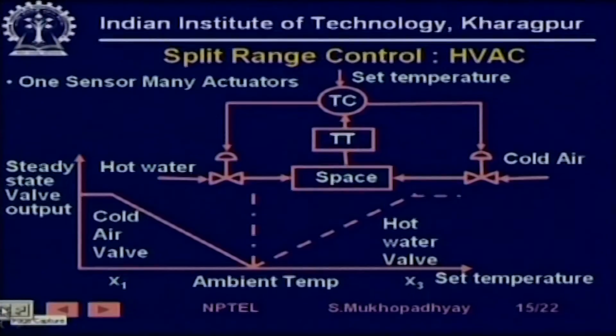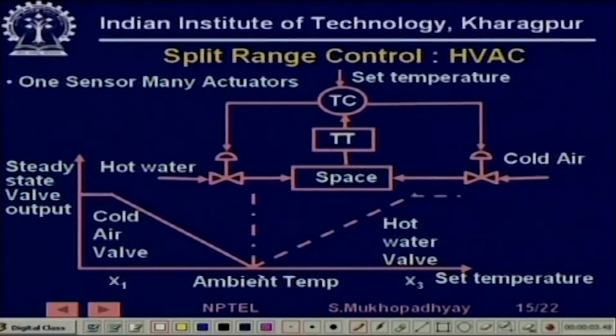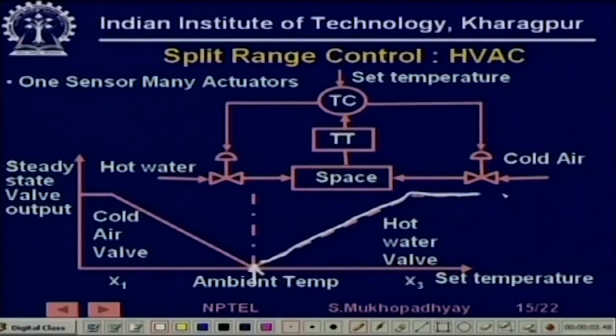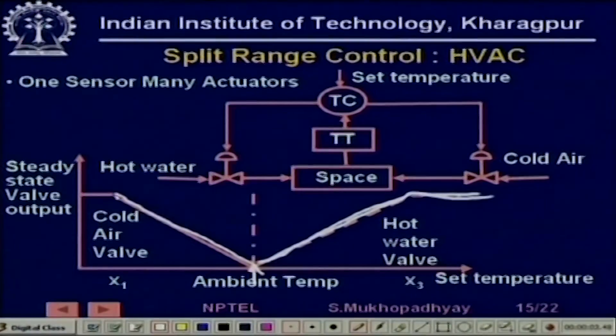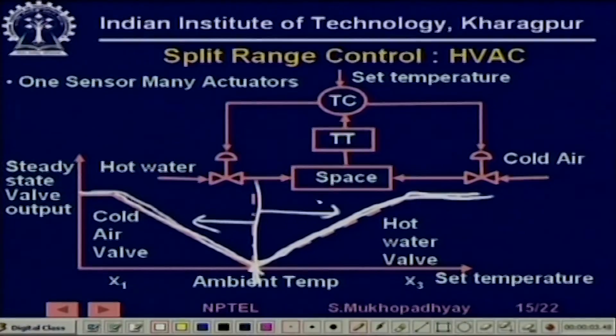When the set temperature is greater than ambient temperature, you use the hot water actuator, and as the error increases the hot water valve gradually gets opened. The overall control input to the process rises gradually and then becomes stable. Similarly, when the set temperature is below ambient temperature, the cold water valve characteristic is followed. The overall control input characteristic spans the two ranges — in one range you operate the cold water valve and in the other range you operate the hot water valve. This is the standard HVAC control of spaces, which is why it is called split range control — the range is split into two different control modes.